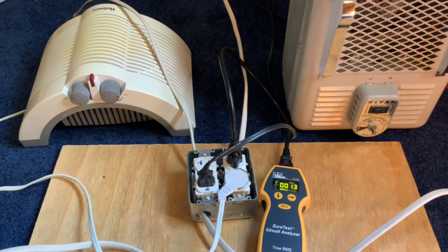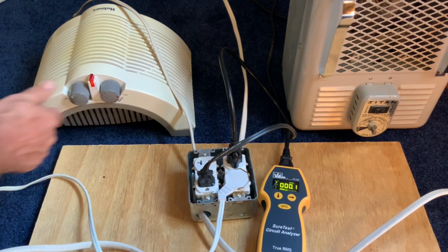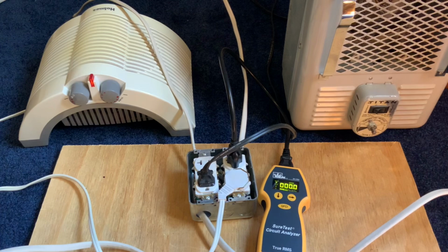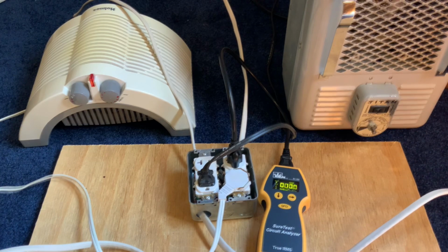Now, if I turn both heaters on, I'll see 1.3 volts dropped with the first heater on, but turning the second heater on, I'm actually canceling out that current on the neutral wire. So I see 0 volts ground to neutral, even though both of these heaters are on and both of these heaters are drawing 10 amps.